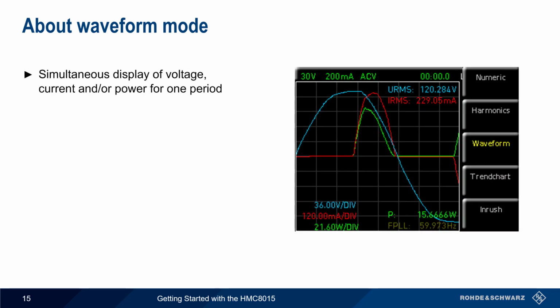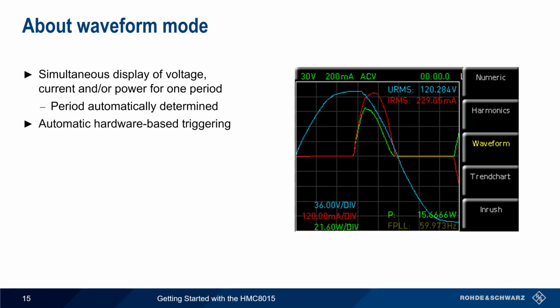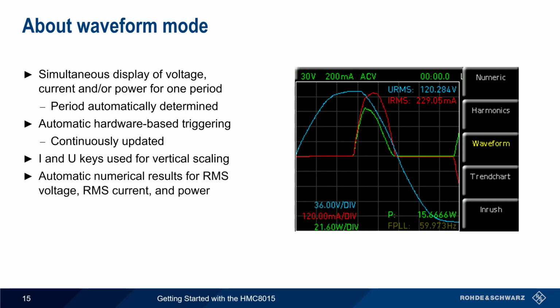The next mode we'll look at is Waveform mode. This mode provides a graphical view of voltage, current, and/or power over one waveform period, similar to how these would be displayed on an oscilloscope. The period is automatically determined by the HMC. An automatic hardware-based trigger is used to start each acquisition, and the waveform is continuously updated. Vertical scaling of the waveform can be done using the I and U keys on the front panel. In addition to displaying the waveform, the HMC also provides numerical results for RMS voltage, RMS current, and power, with soft keys being used to choose which traces to display or hide.